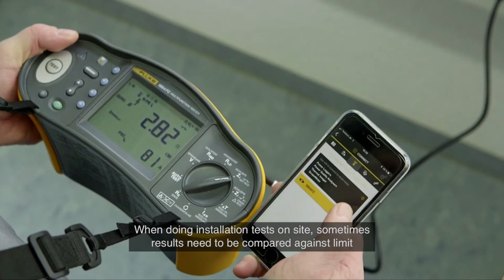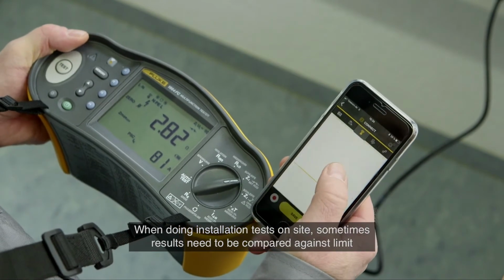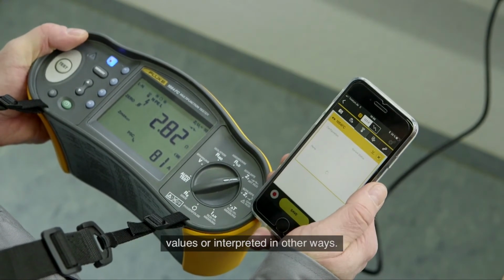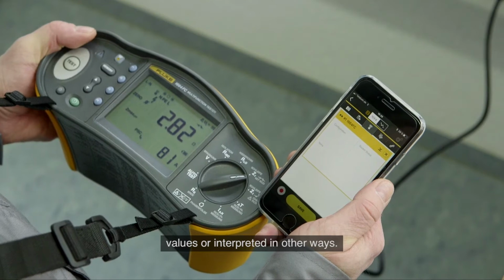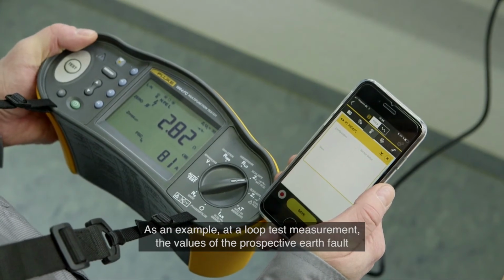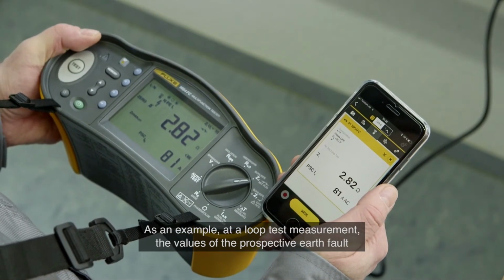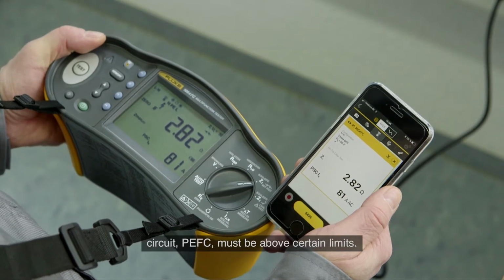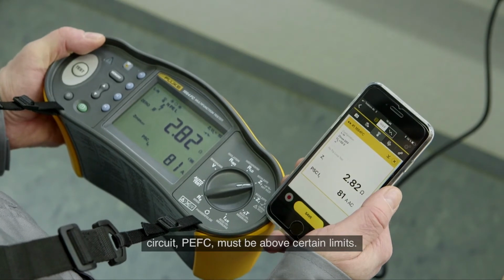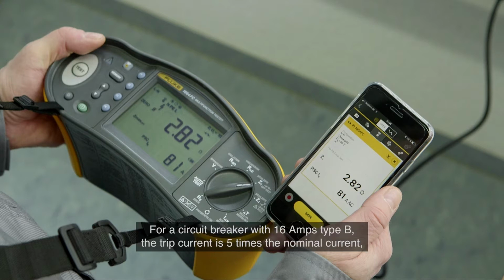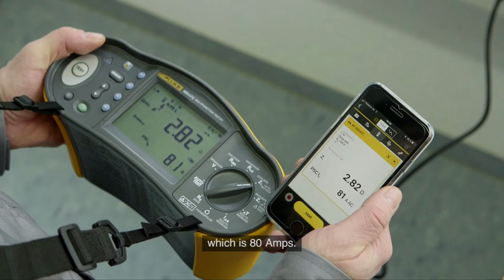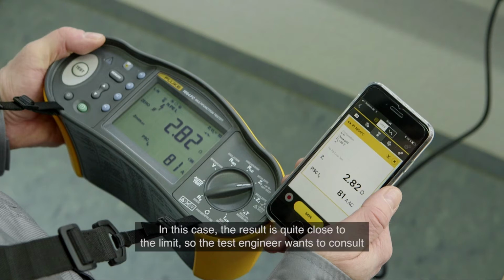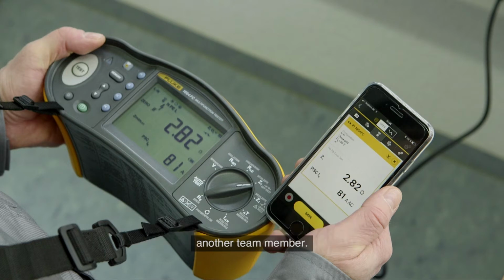When doing installation tests on site, sometimes results need to be compared against limit values or interpreted in other ways. For example, at a loop test measurement, the values of the prospective earth fault circuit (PEFC) must be above certain limits. For a circuit breaker with 16 amps type B, the trip current is 5 times the nominal current, which is 80 amps. In this case, the result is quite close to the limit, so the test engineer wants to consult another team member.